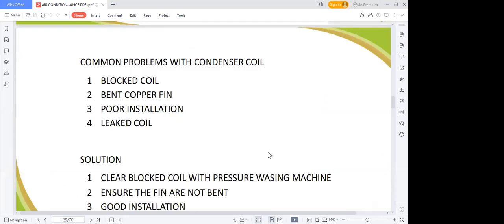So, common problems with your condenser coil: blocked coil. What blocks the coil? Dust from the air. You install your equipment where there's too much dust. Each time it's working, it's sucking in dust, and within time, it's blocked. So the solution is to buy what they call a pressure washing machine. I believe most of us have seen one. If you have not, we have a similar one used for your car. When you stay in an environment where your radiator is always blocked or overheating, your mechanic tells you the radiator is blocked and you need to wash it. Similar things happen in your AC. Once it's blocked, you need a pressure washing machine to pump out the dirt. It's one of the requirements for your maintenance: you must wash the outdoor units to make them look new.